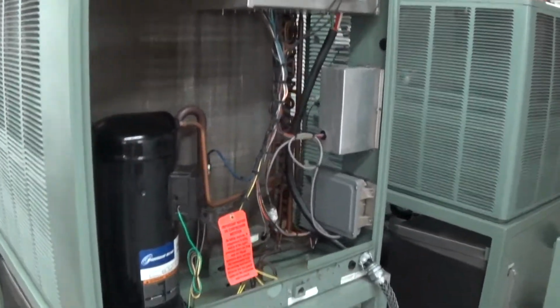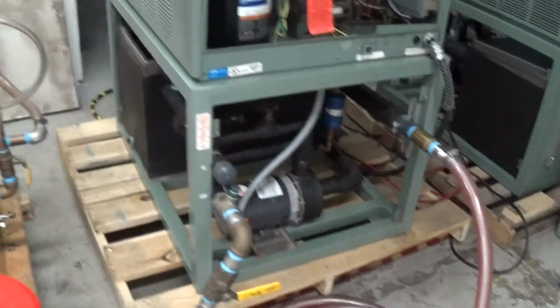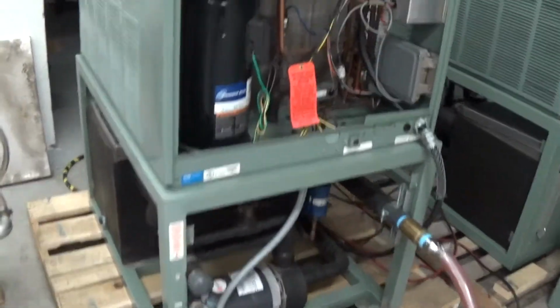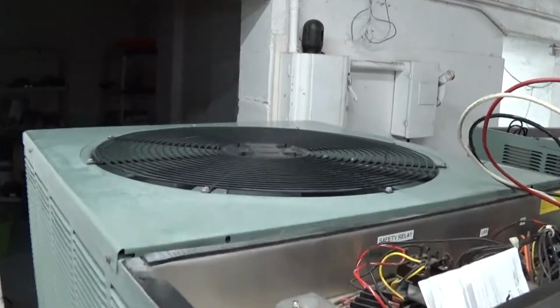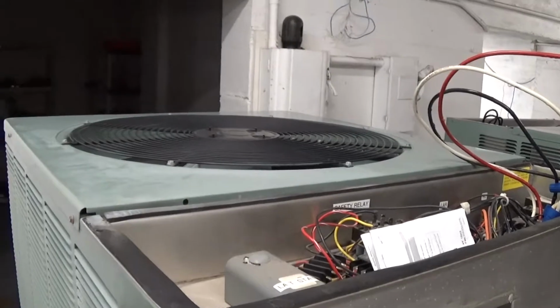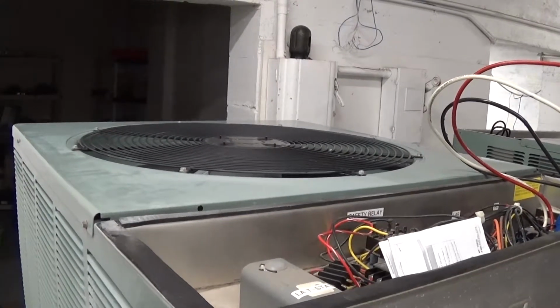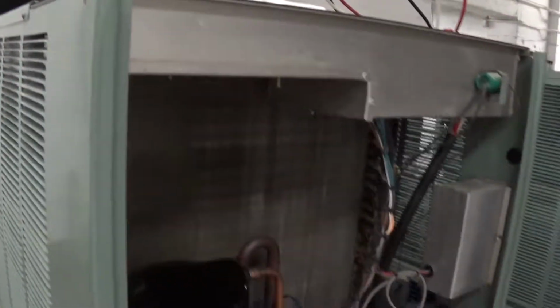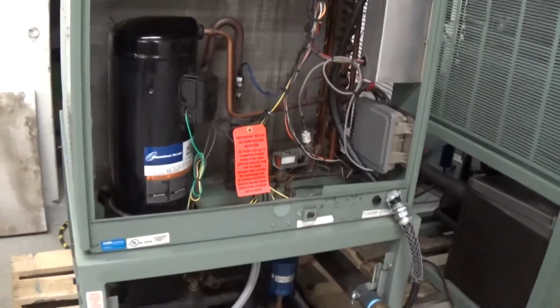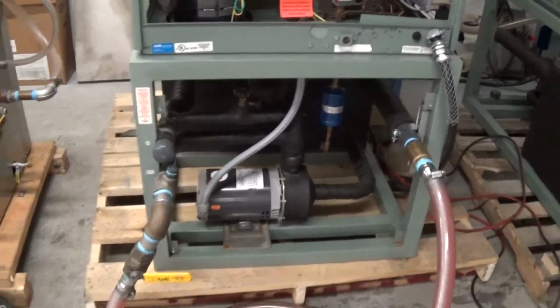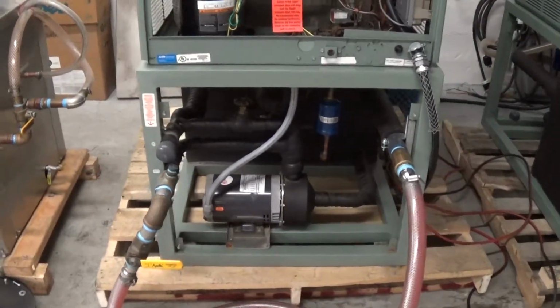and get it running. We do have all the covers and side covers, but the way this cold shot chiller works is our condenser is here, so there's no side covers that can be off that would inhibit or prevent appropriate flow through the condenser. So for our tests, we usually leave the side covers off just so we can point out a few things.